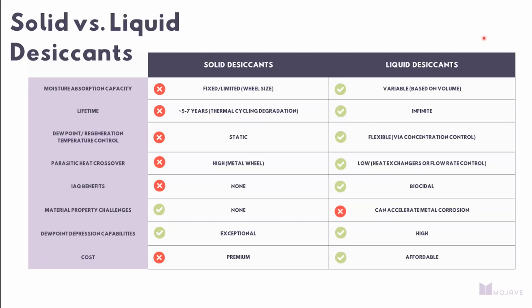Solid desiccants, you have a wheel that's rotating between airstreams, so you get parasitic heat crossover. Solid desiccants have to be regenerated up into the 200 to 300 degrees Fahrenheit range to get all the moisture they've trapped out, so the process can be repeated. There's a lot of parasitic heat crossover between airstreams as a result of that. With liquid desiccants, there's very low, and frankly, with our product, negligible crossover of heat between the airstreams because we're not really interfacing the airstreams. They're isolated. There's negligible amount of heat being brought over in our liquid desiccant as a medium.